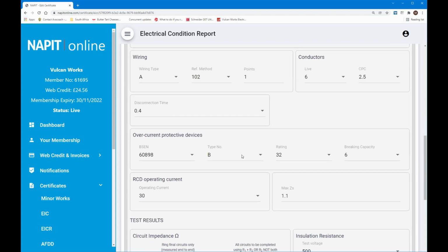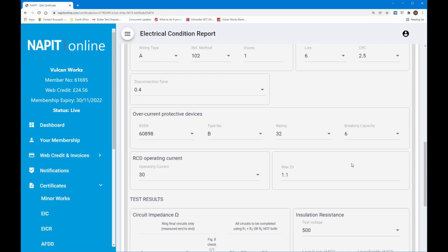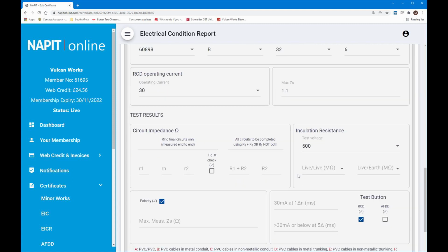Disconnection time is a normal 0.4. So the overcurrent device for this one is a BS EN 60898 type B, and it's a 32 amp rating with a breaking capacity of 6 kiloamps. The RCD operating current is 30, and the max Zs for a 32 amp breaker is 1.1. This is a radial, so we're not worried about ring final information. So the R1, R2 details.